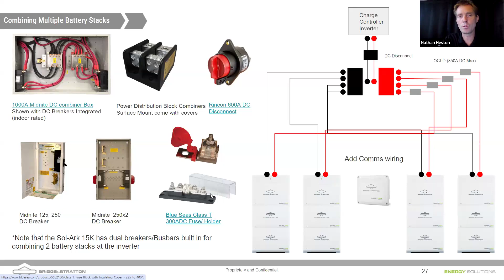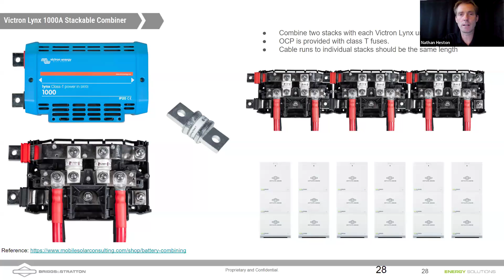There are other ways to do battery combining. Daniel and I were just talking about using a 1000 amp bus bar with a surface mount fuse available in 300 amp ratings. I'll also show an example using a Class T fuse together with a Victron Lynx unit. Make sure you get the Lynx unit with Class T power in, in a 1000 amp combiner configuration. These are stackable, with individual fuses on the positive coming into the bus bar. Make sure you get the Lynx that accommodates 4-aught cabling, and use 4-aught cabling from each of your stacks.